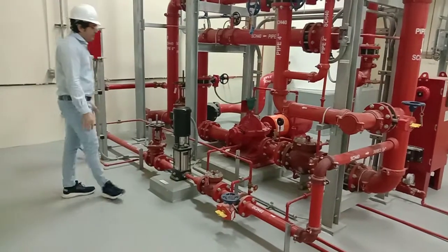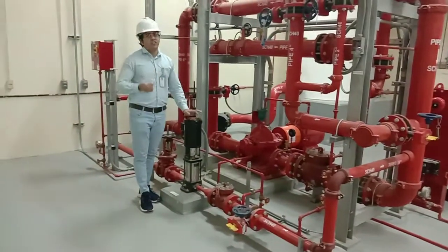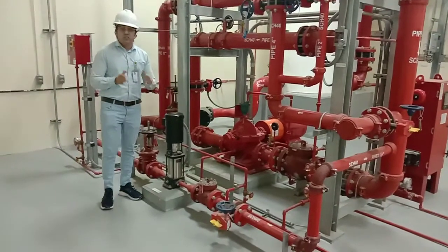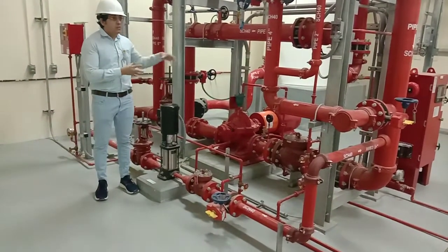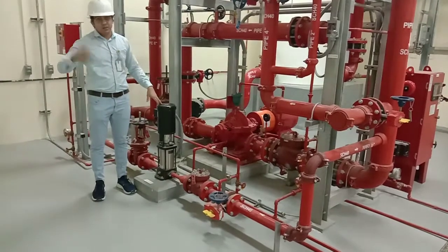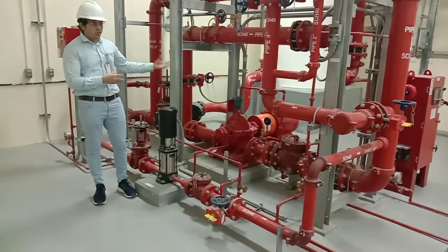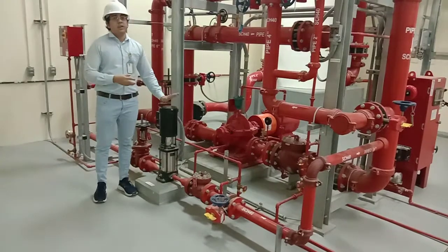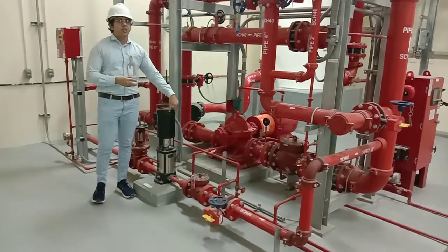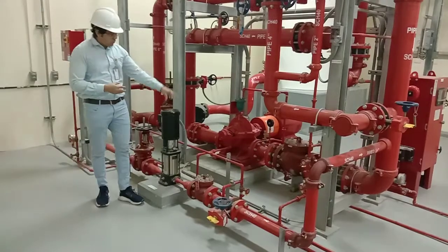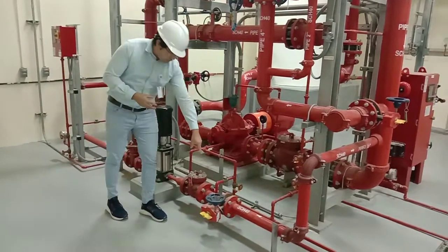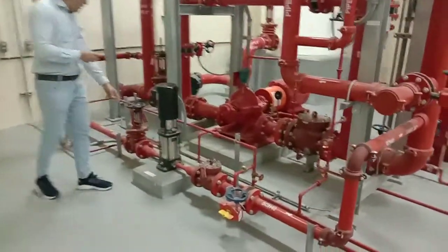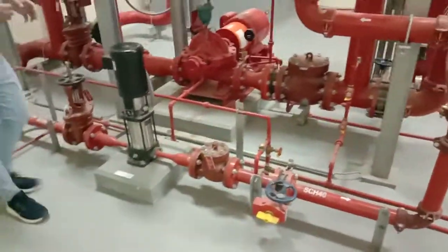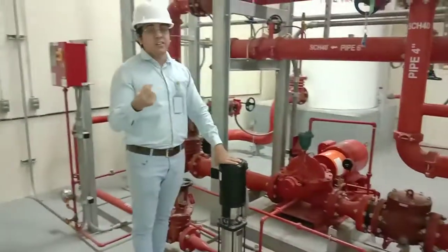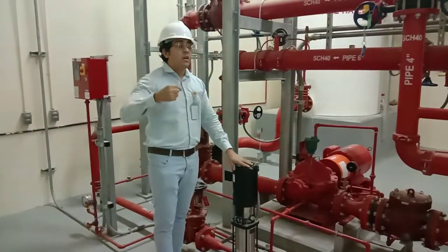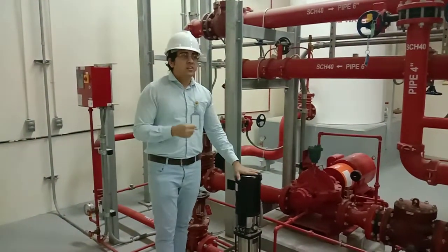Now, as I said, this is not a pump to fight the fire, just to maintain the pressure in the fire protection system, right? To save the life of the main pump. It will go up to 20 years without any problem of damage to the bearing and all. So this one need not be listed. What is the meaning? There should be no requirement for UL or FM, either for the jockey pump or for the valves we have in the jockey pump. We don't need this to be listed, because normally we need listed or approved material for something which is for fire protection. This is just maintaining the system.